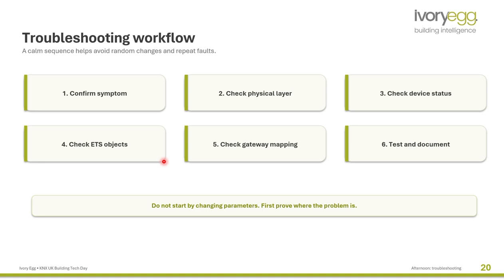The troubleshooting workflow is to confirm the error, check the physical layer, check the device status, check the ETS objects, check the gateway mapping, then test and document. In my opinion, for your ETS project you can check through ETS online with the group address check, and if you have BACnet you can check your network as well.